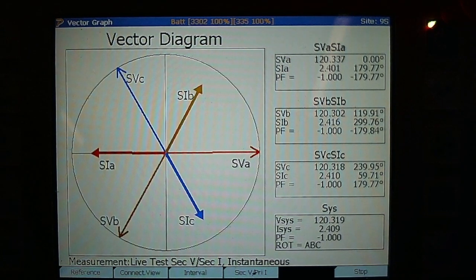Typically, a large majority of the time, it's going to be the connections on those secondary terminals on that CT. So in this case, I'm looking at this. We always talk about possibilities. I'm out here in the field, and I look at this, and I think, what could be the possible issues here? Because those are some jacked-looking vectors initially, right? So I'm looking at it.